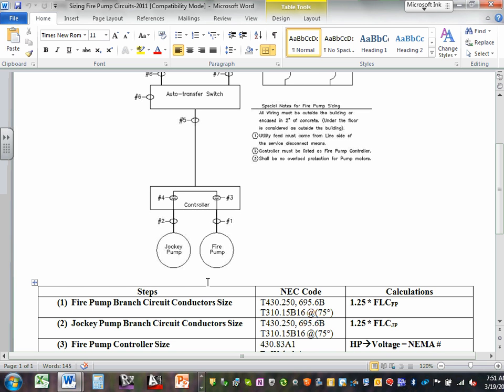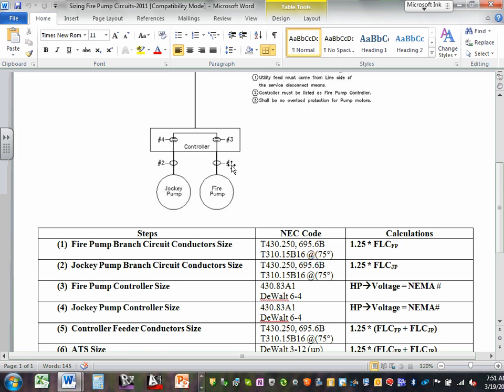Everybody can see that? So starting from the bottom, I have 1, 2. 1 is the fire pump branch circuit conductors. 2 is the jockey pump branch circuit conductors. And 3 is the fire pump controller. 4 is the jockey pump controller. And right next to here is where you find the code references to them. And the last column is how do you calculate these? So on the test, you grab that piece of paper in front of you, and you apply it.